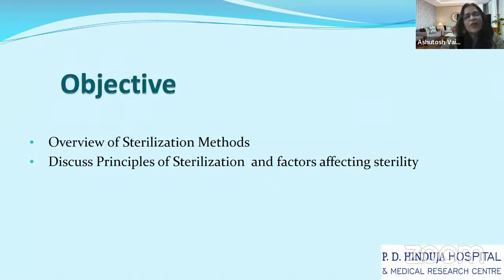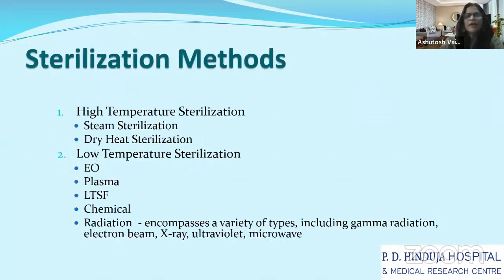The objective here is to have an overview of sterilization methods and discuss the principles of sterilization and factors affecting sterility. As we are all aware, sterilization methods can be categorized into two categories: high temperature and low temperature. In high temperature, we have steam sterilization and dry sterilization. Steam is moist sterilization, so there is some percentage of moisture, and dry heat is absolutely dry. The low temperature sterilization includes gas sterilization, which is EO, then plasma, then LTSF. LTSF is low temperature steam formaldehyde, a combination of low temperature steam and formaldehyde.